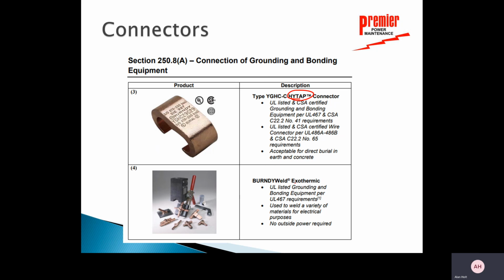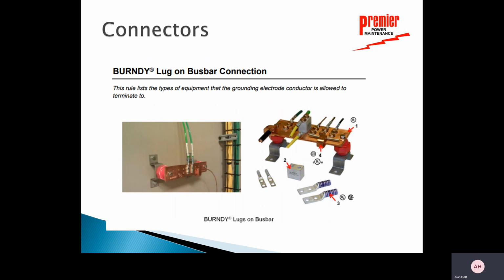I can see the exothermic bonding, which is the CAD weld. Brad Moore and the construction group does a lot of CAD welding. Don't need any outside power, which is not much a concern anymore with the advent of battery-powered compression tools, but used to have some utility power, some source of power there to do some work, but now it's not required. I can have lug-on bus bar connections, so I can actually land my own ground bus, again, separately from everything else. I can have lugs screwed to it, again, compression. I can list separately there.